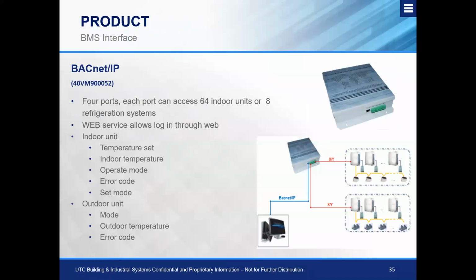Now, as far as upper level controls go, we have our BACnet over IP interface, and this is to be able to tie into an existing BACnet system. All it's doing is taking the Carrier VRF language or protocol and converting it over into BACnet protocol, which we can then broadcast to the existing control system. And with this, you get your temperature set points, indoor unit temperatures, operating modes, error codes, and different schedules that you can set up through the actual interface itself. And then you also get your outdoor unit mode, outdoor temperature, and any associated error codes on that outdoor unit that are active, and also a history of them.